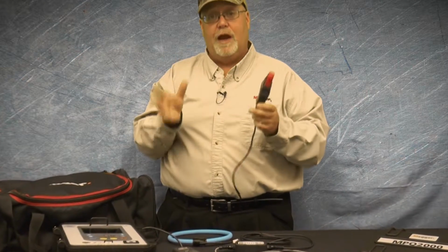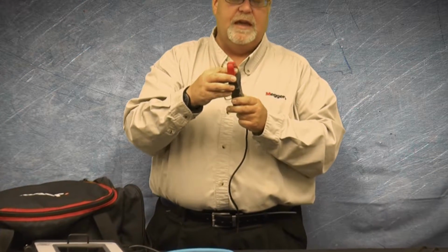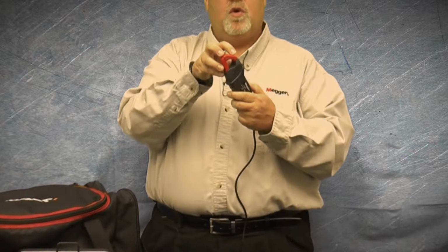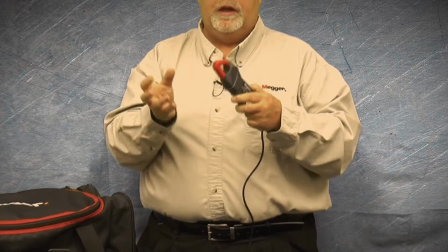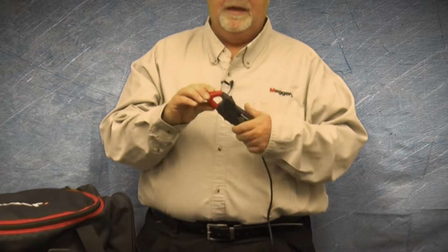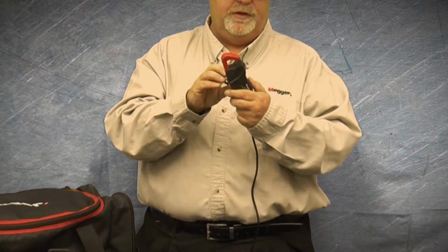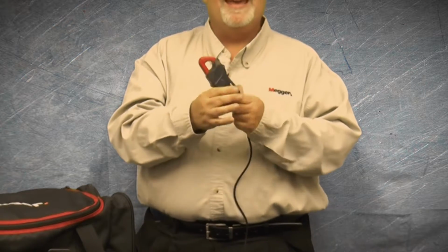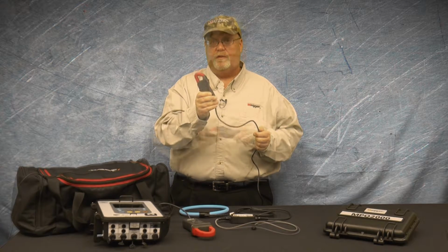The current in the primary, in this case the wire that the CT is around, induces a magnetic field in the core, which is then transferred to the secondary, inducing a proportional current in the secondary. The split core CT is a passive CT with a high permeability core. It's the changing magnetic field that induces the changing current in it. This type of current clamp can be only used to measure AC current.